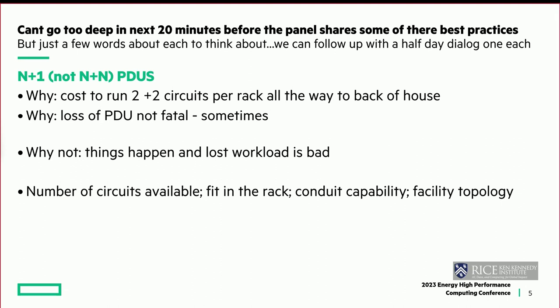One thing we did is for Frontera, we actually have 415 bus bars up above the ceiling, and instead of doing the IEC 309 connector, we actually hardwired the PDU into the bus plug. We did blow one of our bus plugs during our power event. We actually had a bus plug blow, and the vendor's like, can you send that back to us? We need to figure out how that failed.